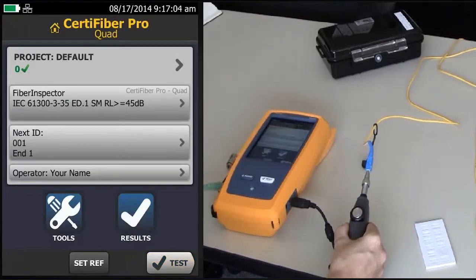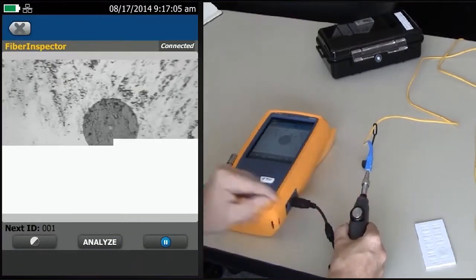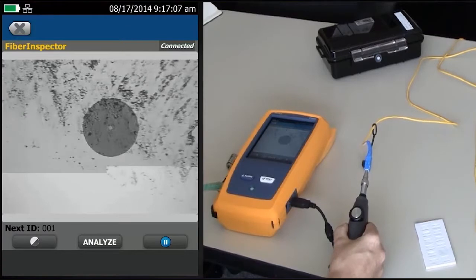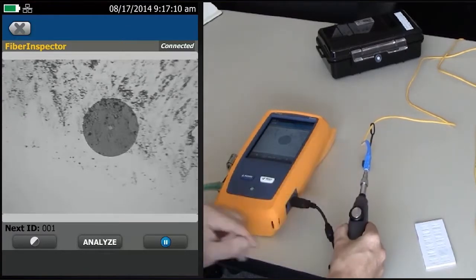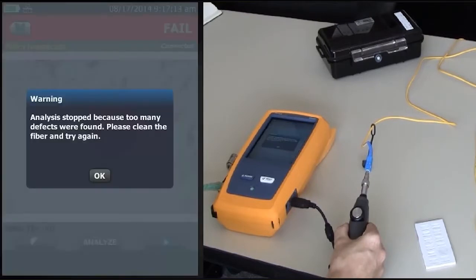And if I hit Test now, the difference this time is you'll see the Analyze option. And if I've got that focused in, now if I tap Analyze, it'll stop because too many defects were found. Please clean the fiber and try again.